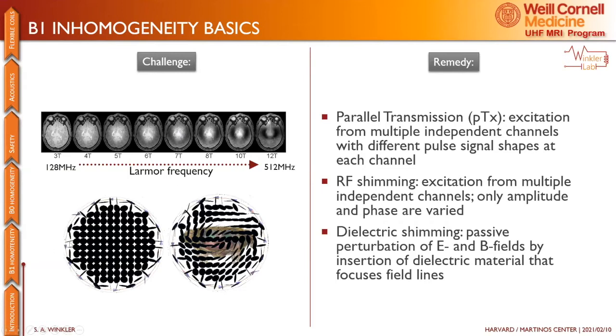If you look at this in a different way, in the ideal magnetic resonance experiment, what you want is a circularly polarized signal for the B1 field. But as you load it with tissue, you actually deviate from the circular polarization. You get elliptical polarization and linear polarization, even in some cases. And on one hand, that causes signal loss, and on the other, phase shifts and all kinds of complicated things. So what people do to remedy this, popularly recently, is parallel transmission.